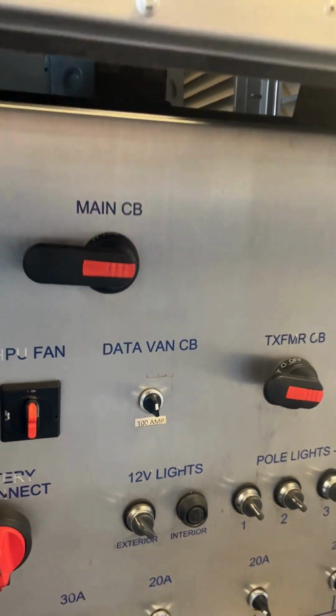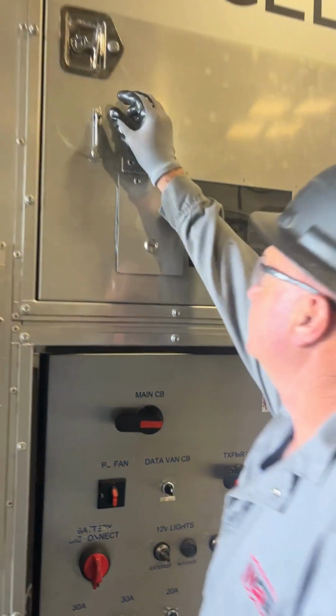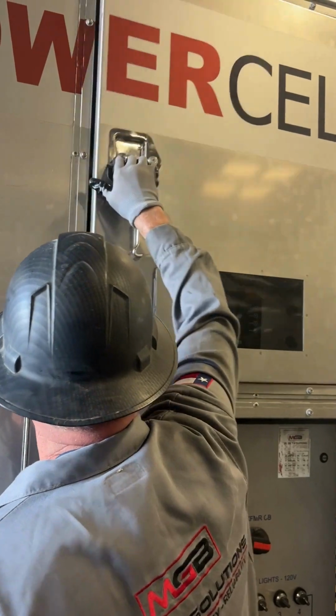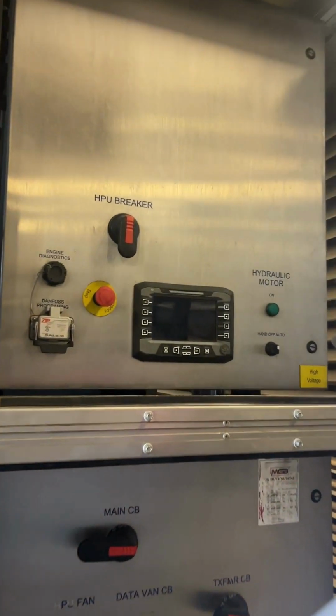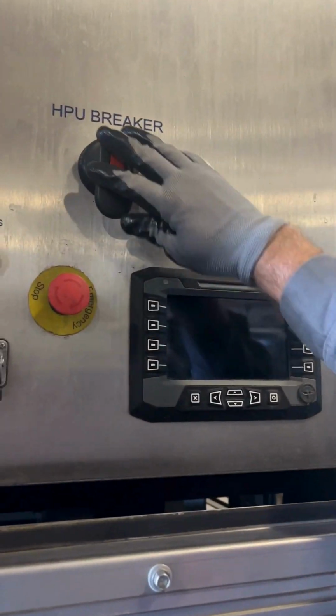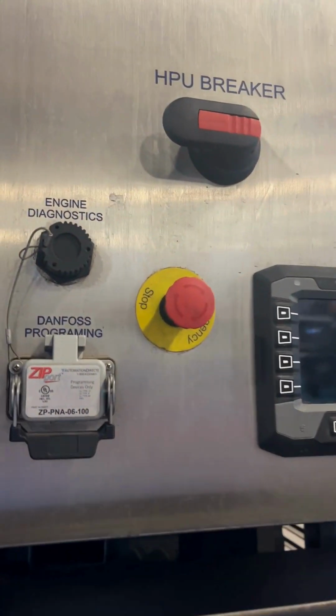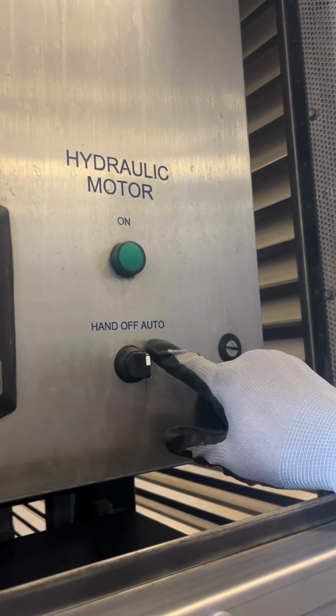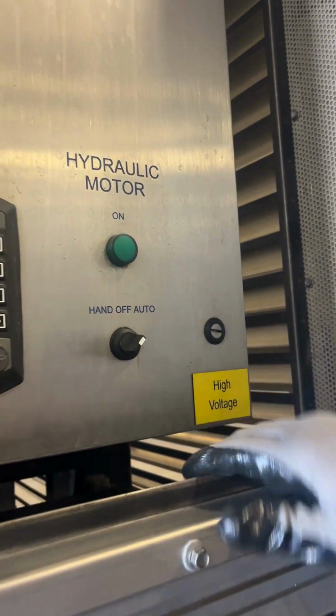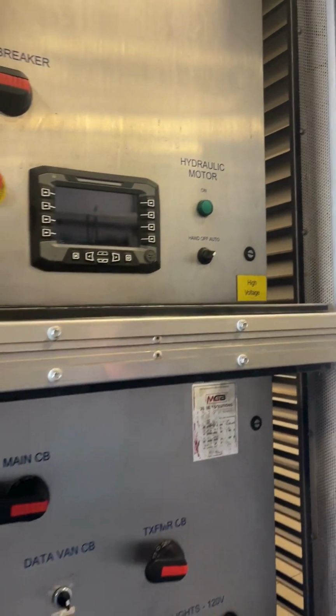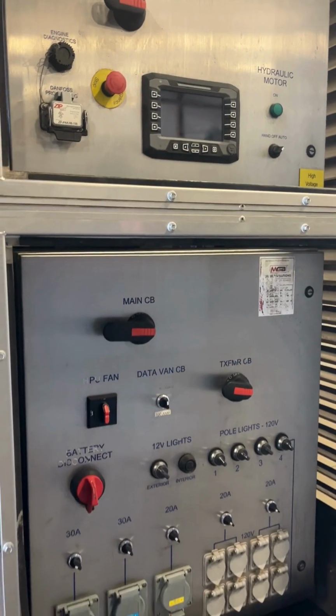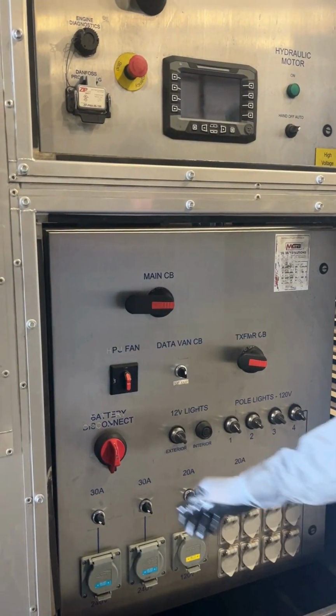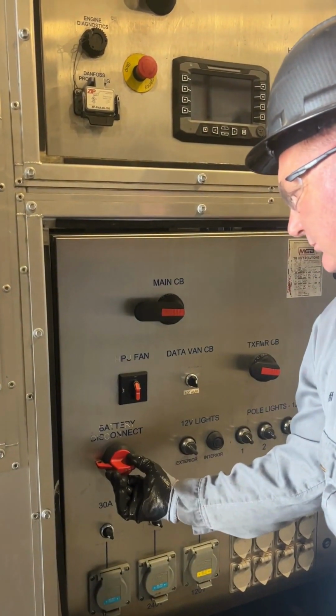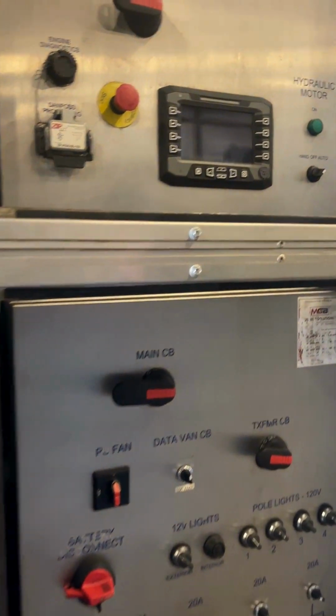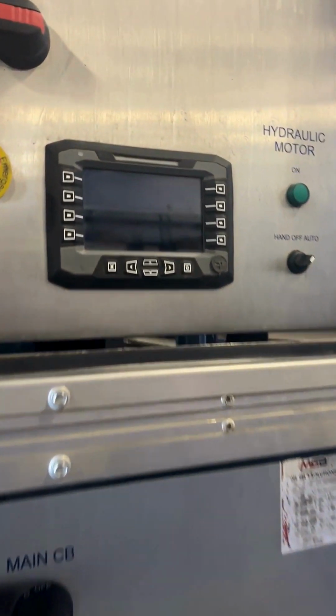And then you're going to open the top door. What we want to make sure here is that the main HPU breaker is in the on position, that the emergency stop has not been activated, and that the HPU motor controller is in the auto position. Once all of that is verified, you can proceed to switch on the main battery disconnect. This will power on the unit and allow the computers to boot up.